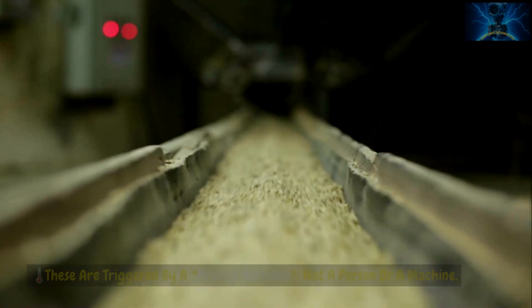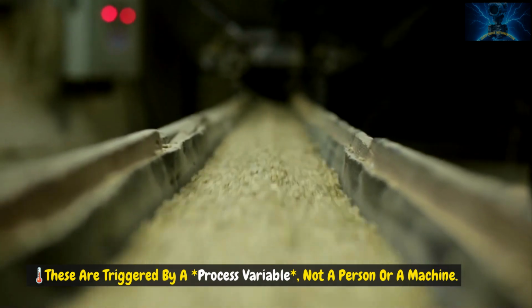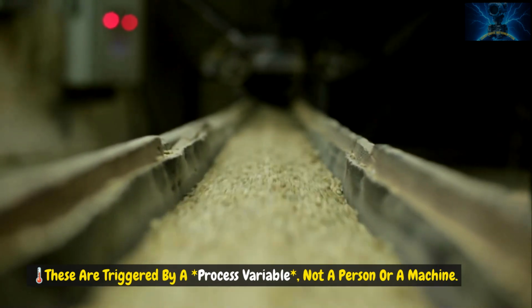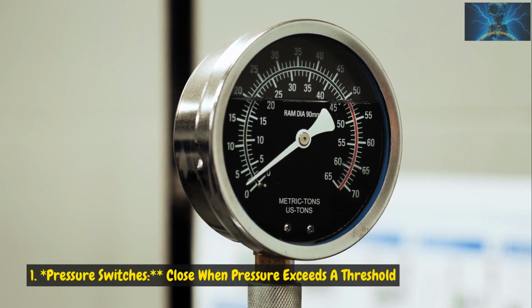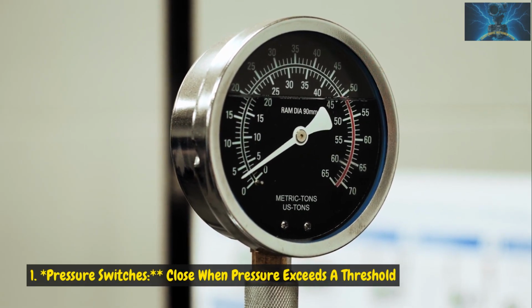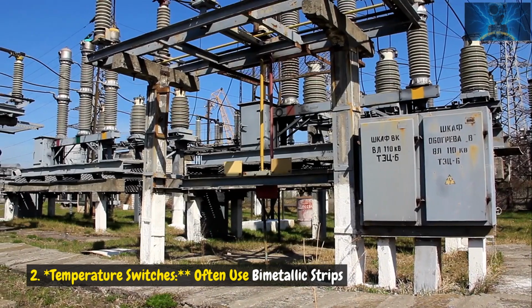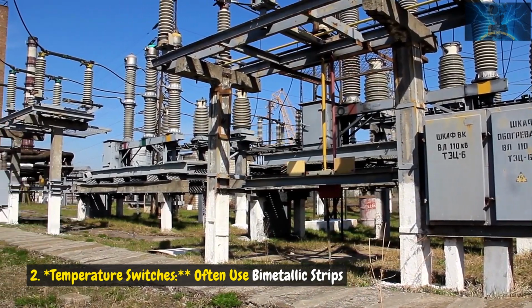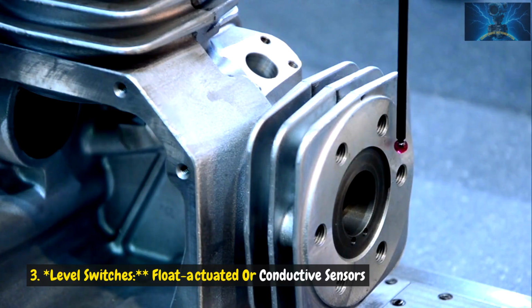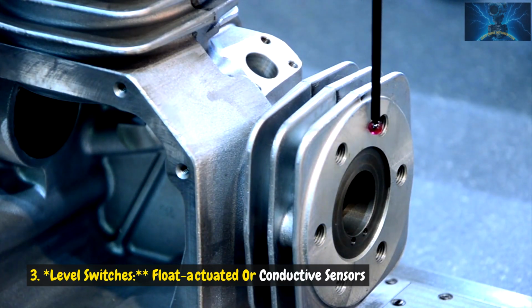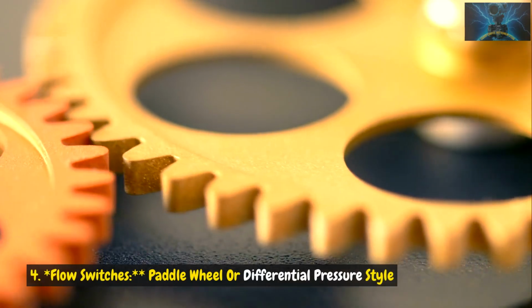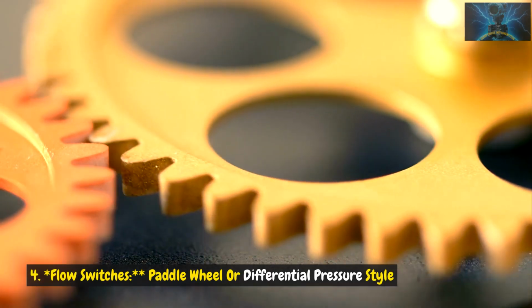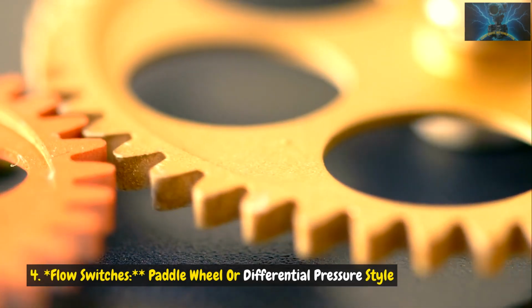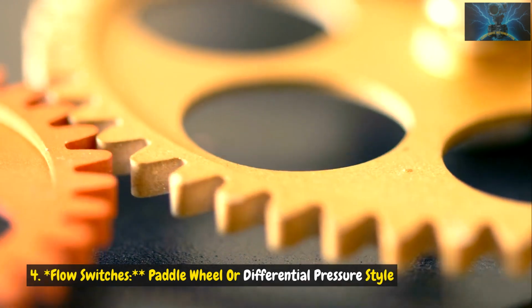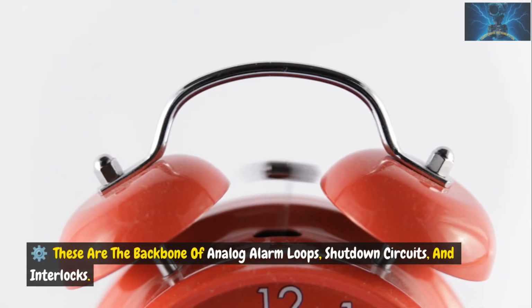Process switches. These are triggered by a process variable, not a person or a machine. One, pressure switches. Close when pressure exceeds a threshold. Two, temperature switches. Often using bimetallic strips. Three, level switches. Float-actuated or conductive sensors. Four, flow switches. Paddle wheel or differential pressure style. These are the backbone of analog alarm loops, shutdown circuits, and interlocks.